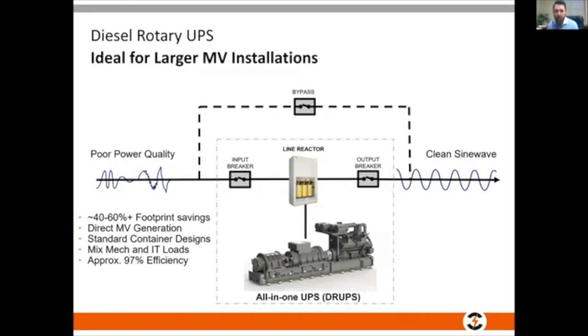In addition to what Scott had said, we see a lot of medium voltage applications. I can do medium voltage direct generation with no need for transmission up or down. This can be a 15 kV source—I'll just supply you a 15 kV alternator with 15 kV breakers. For many applications, we're doing solutions at the substation, backing up the entire building. We're no longer isolating IT and segregating mechanical separately—we're backing up the whole building, and it's much easier with the flexibility of doing that at the native voltage, which in this instance could be 15 kV.